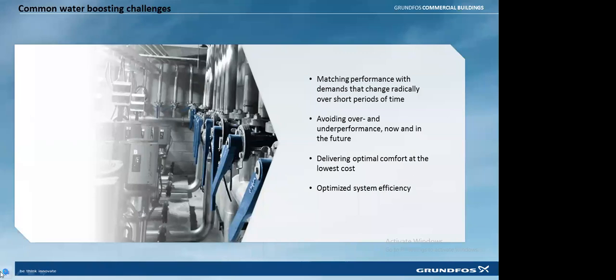Before going into that, what are the common issues we face with hydro-pneumatic systems in a facility? The main important thing is there is a huge variation in the water consumption pattern. That can be a sudden surge in the water demand, or a sudden reduction in the water demand, a lot of fluctuation in the entire water consumption pattern. That's one of the key issues. Another thing is underperformance, or sometimes a little over design above our requirement. This is again a major issue we face, under design or over design at that site.